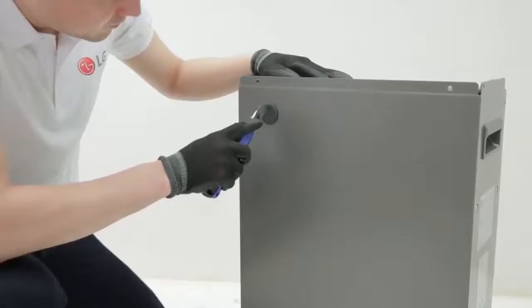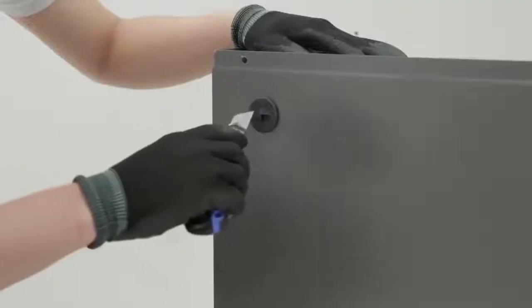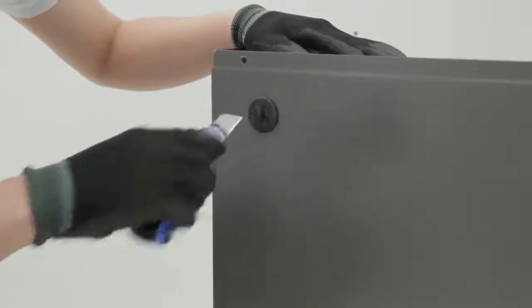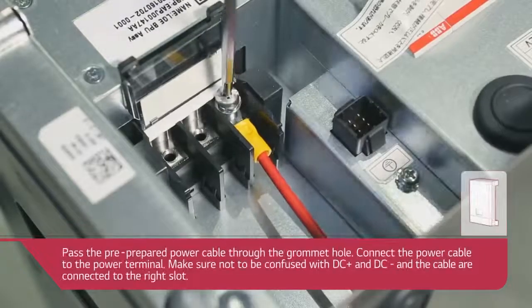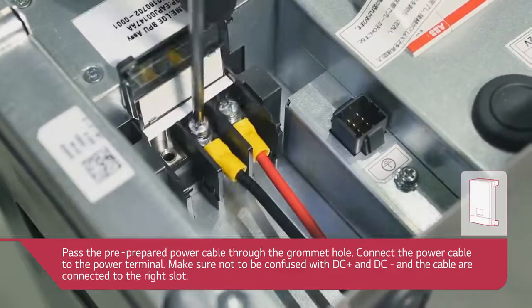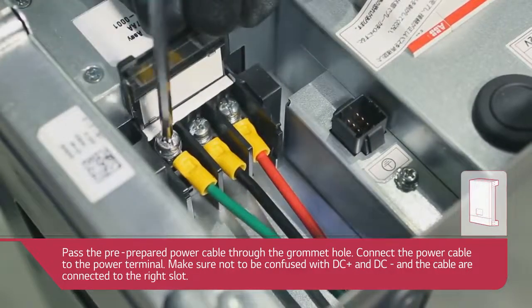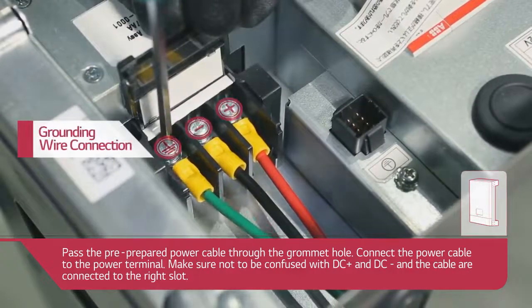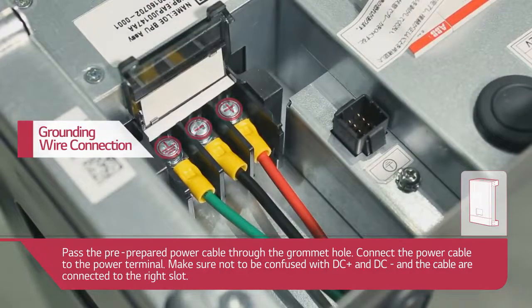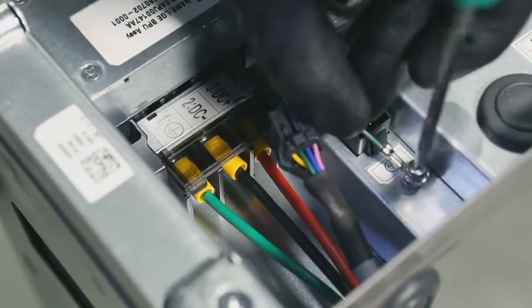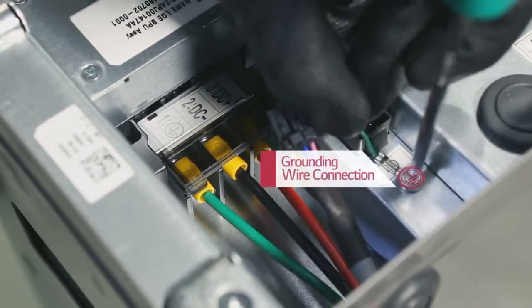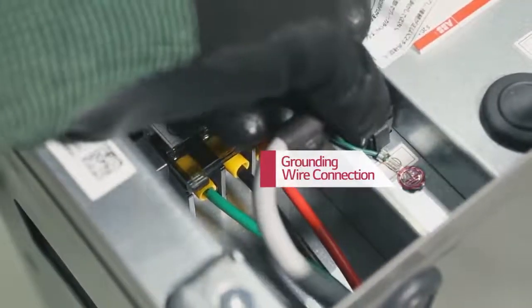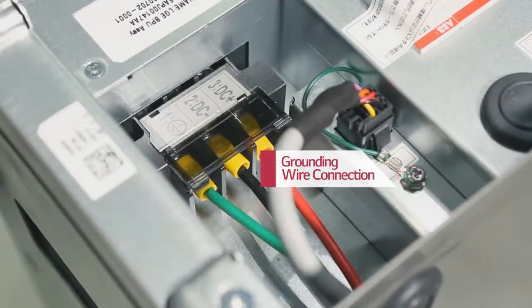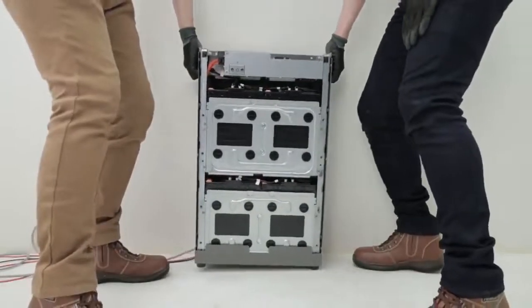Make a cable hole through the grommet by cutting it in crossed lines. Pass the pre-prepared power cable through the grommet hole. Connect the power cables to the power terminal. Make sure not to be confused with DC plus and DC minus, and that the cables are connected to the right slot. And then, connect the battery management system cable to the I/O connector on the battery by passing the cable through the grommet hole. Place the battery back against the wall.